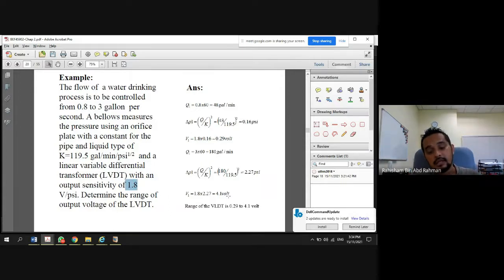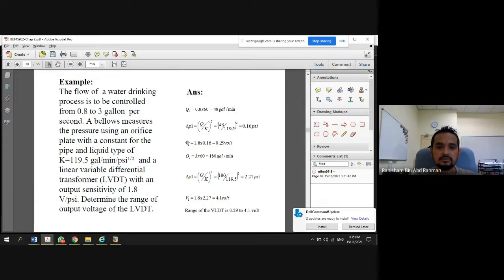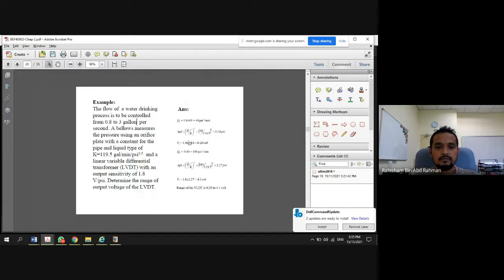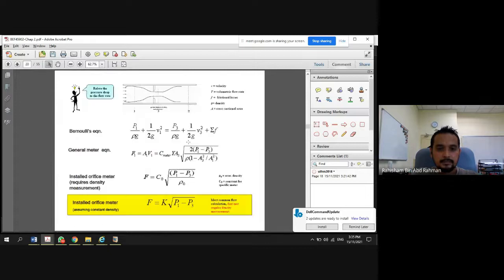Okay, so from here we can know that the LVDT, linear variable differential transformer, reading will be between 0.29 to 4.1. These are the values based on 0.8 to 3 gallon per second. Okay, so that is the range of the LVDT. A very simple formulation. What you have to know, and you have to be very careful here, is this formula.